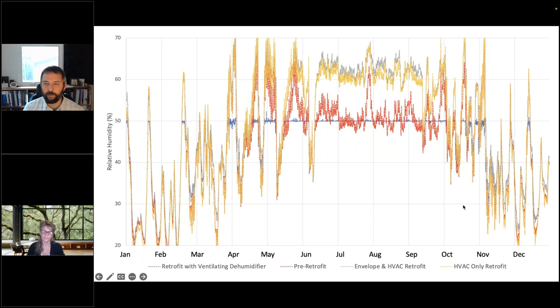A great way to think about this, if you're not into modeling or running calculations, is to pull the weather data for free for a year and look at the dew point versus the dry bulb to guesstimate when you're going to have AC runtime and when you're not. We know interior dew point typically tracks with exterior dew point, so if you have times with high exterior dew points and low dry bulbs where you're not going to get a lot of cooling, that's a situation where you could see big peaks like this, where you might want to put in dehumidification.